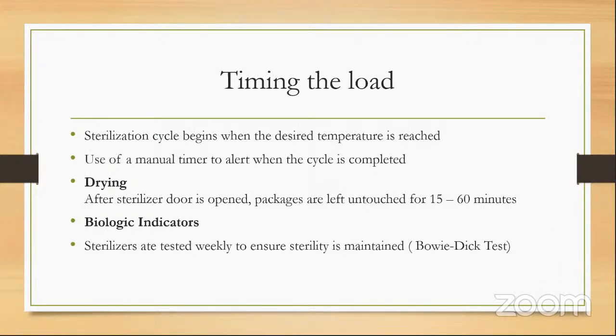Timing the load. The timing of the sterilization cycle begins when the desired temperature is reached. So once the door to the sterilizer is closed and the sterilizer is turned on, it takes a couple minutes for the temperature to be reached. And you can observe that if you stand up to watch it on the dial in the front of the sterilizer. You can use a manual timer, but newer model autoclaves have their own timers that will go off when the cycle is completed.